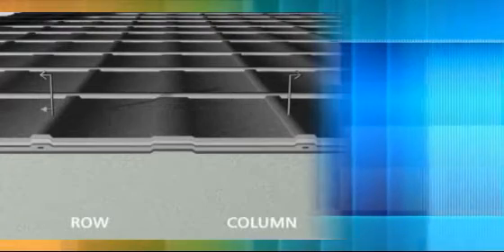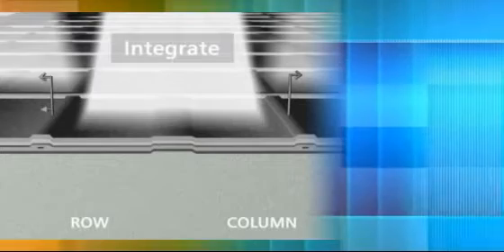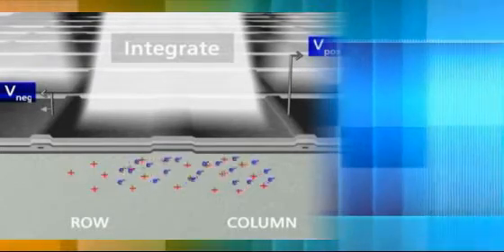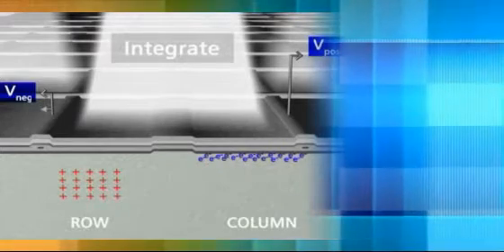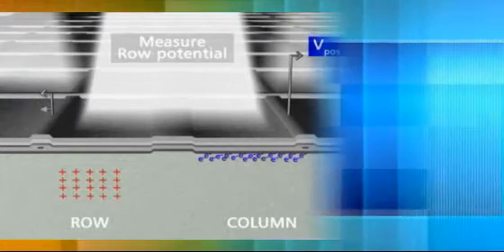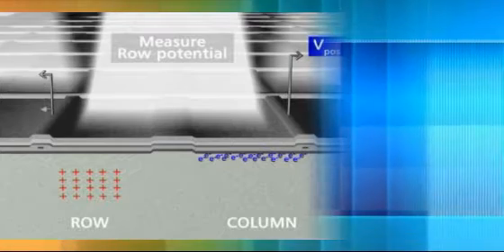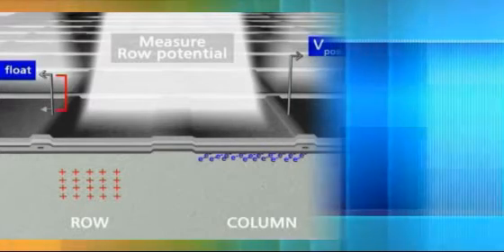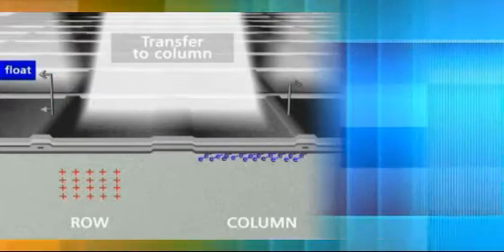Each pixel acts as a photo detector measuring the intensity of the light striking it by converting the photons into electric charge which can be read out and cleared at different rates for each pixel. This is why, unlike other chip based detectors, the CID is resistant to the occurrence of charge overspill or blooming from adjacent pixels receiving high light intensities.